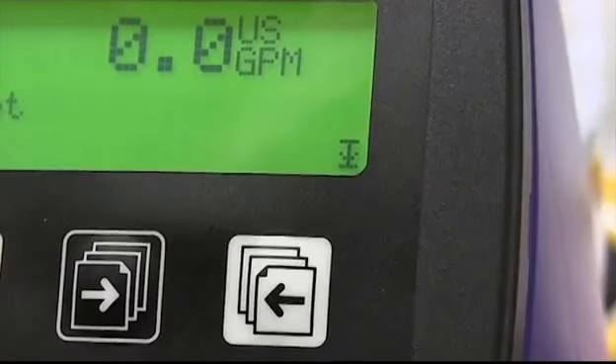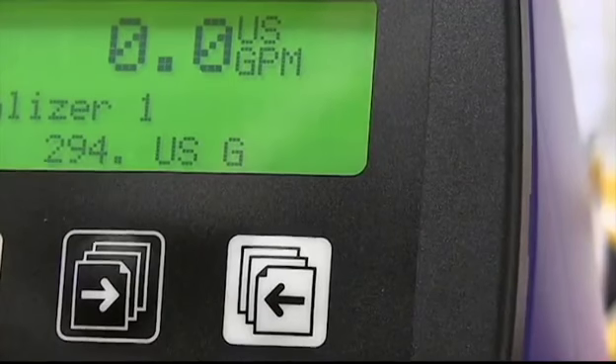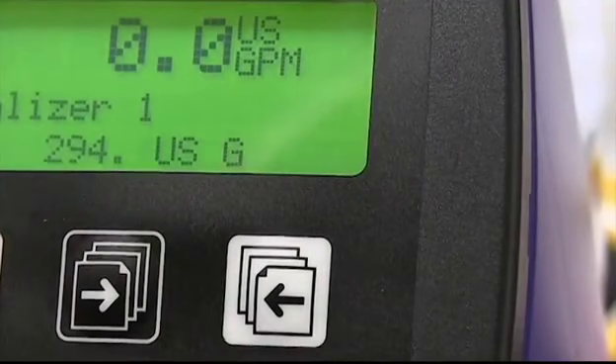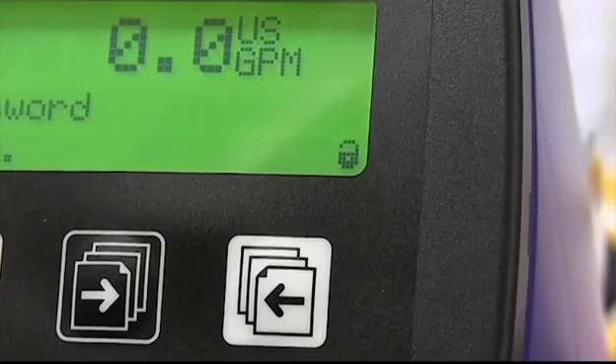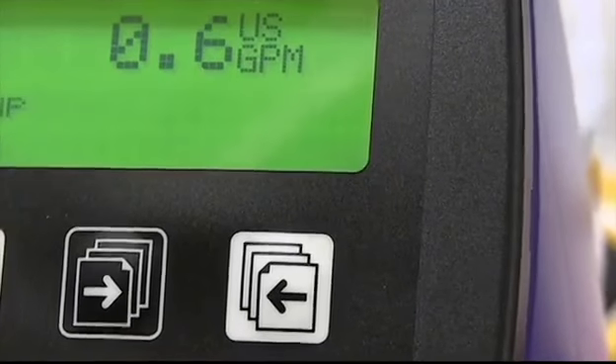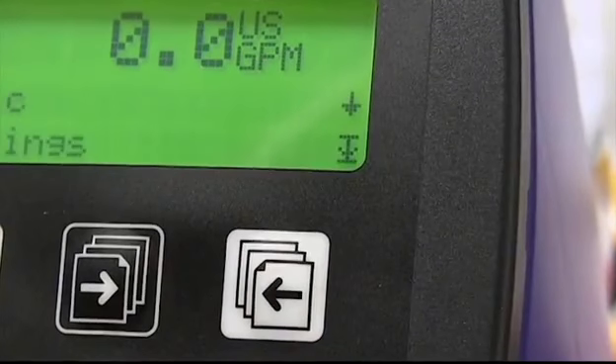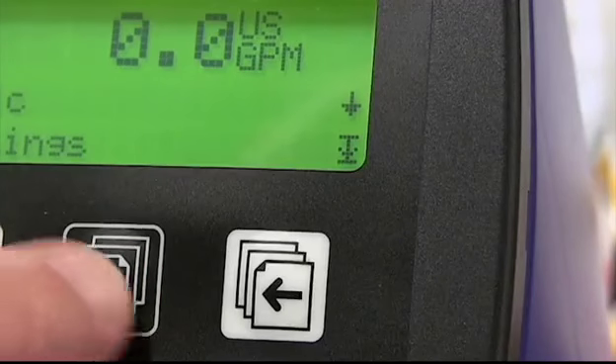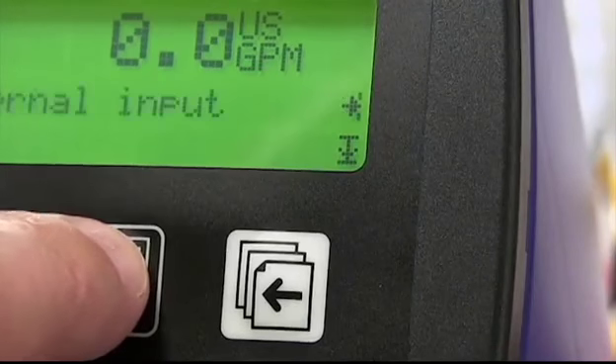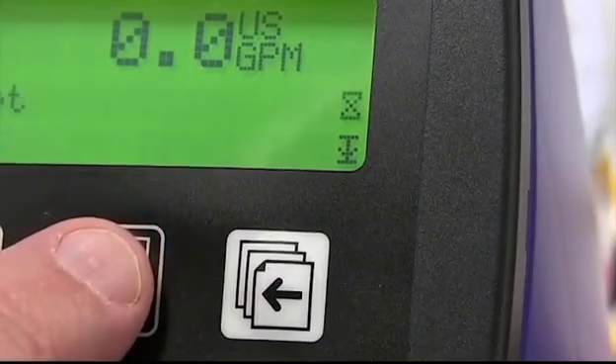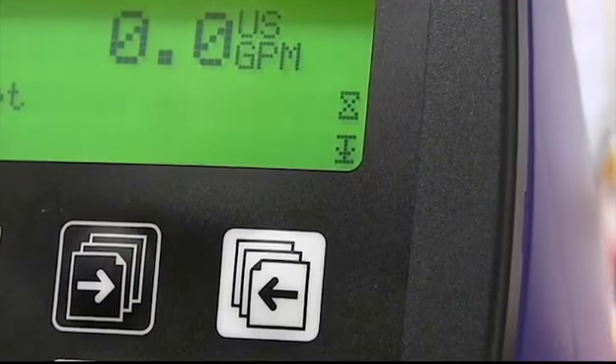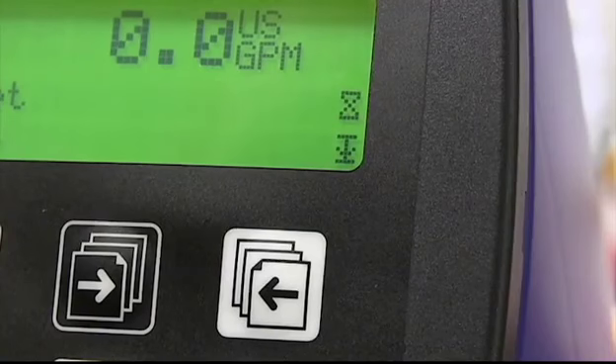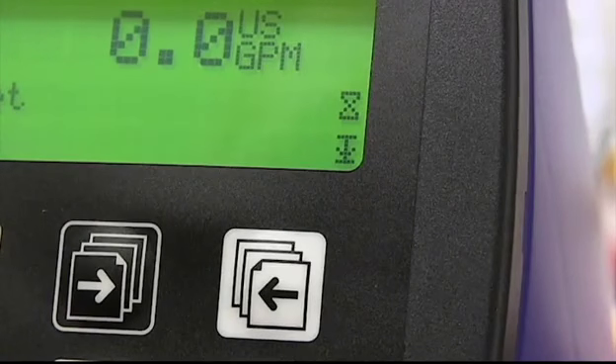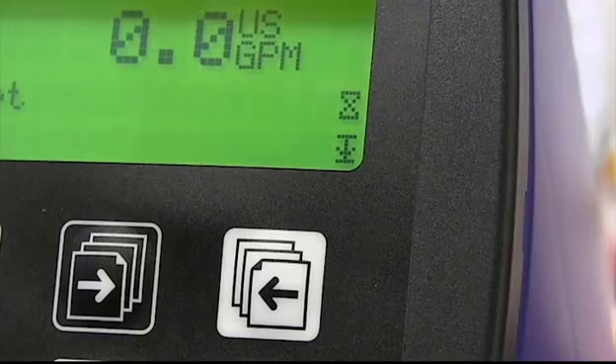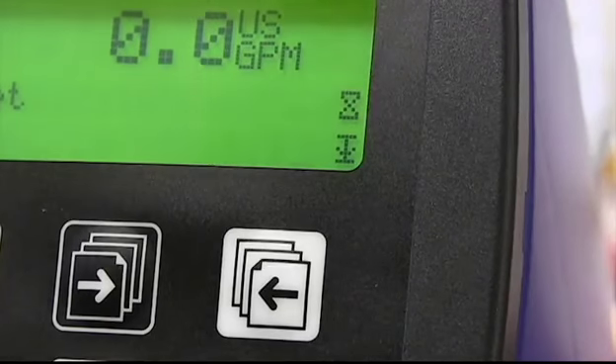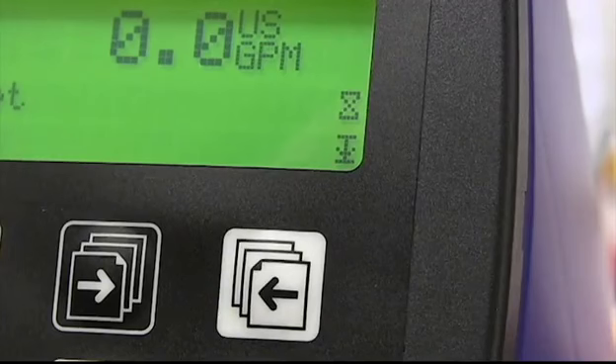Well, we can get out of here. Oops, went too far out. So if you go too far out, hold this in for 2 more seconds. Password again 1000, lock, unlock. Takes you back in again. Press the black page button until you get back to sensor characteristics, reset mode. This is a nice parameter here because should something go wrong with your configuration, you don't know what you did, but something's not right, you can't get out of it, you can reset everything back to factory defaults right here.